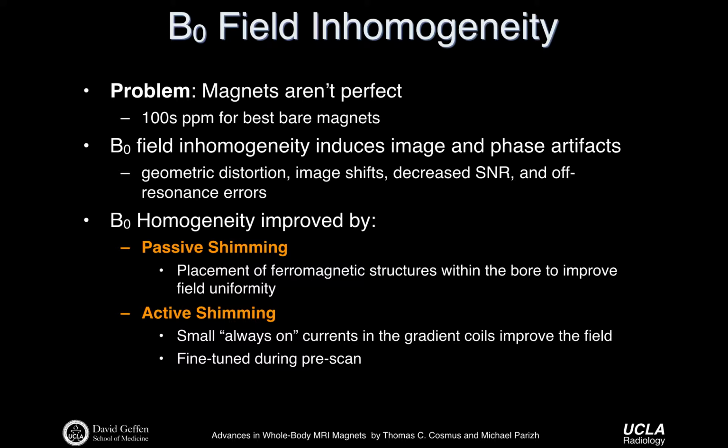Then there's another option after that, which is called active shimming. Every time we scan, every time we put a new object in the scanner, we can tune the field through active shimming.